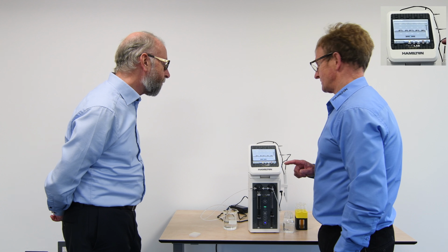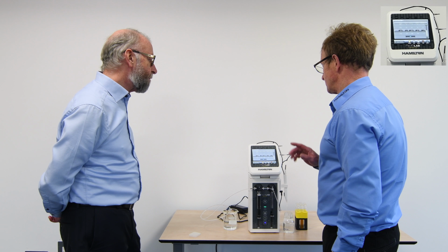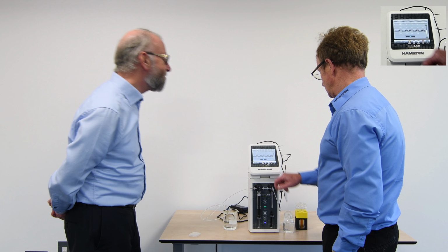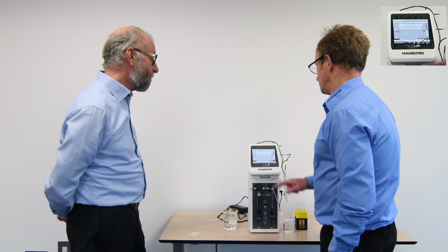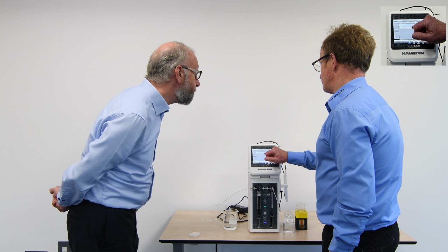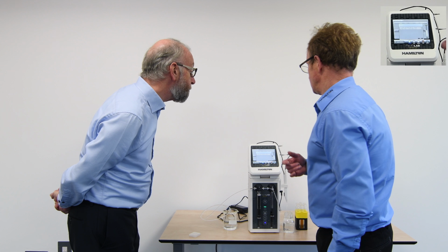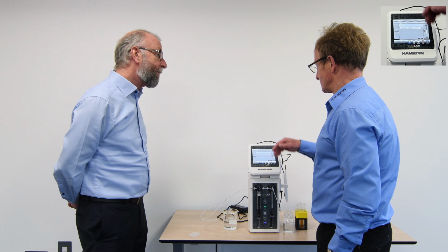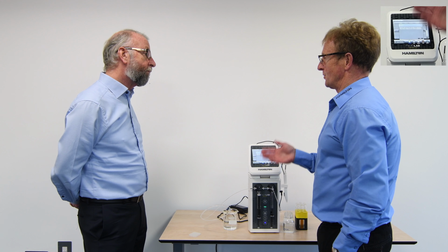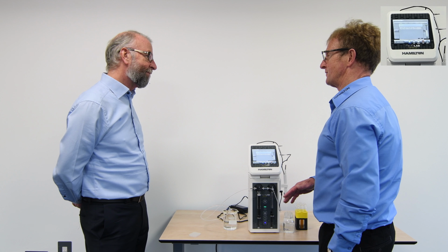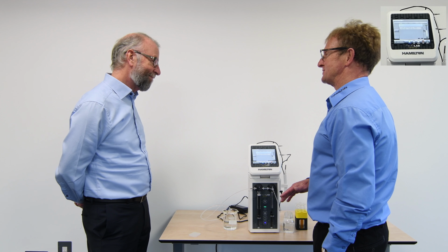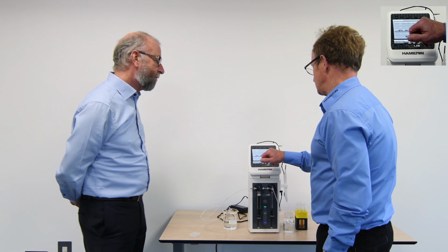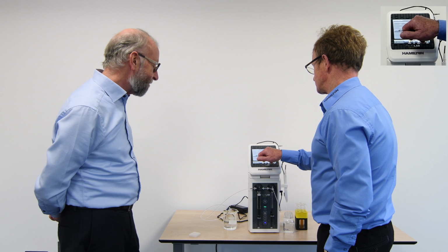Now, if I'd forgotten to actually change the other details, the good step in this is you'll notice this little icon here, it says validate. If I actually press validate here, you'll see this says the method will cause an overaspiration or dispense. So there is initially an error because we've asked it to aspirate more than we're dispensing, and therefore there's an imbalance. It's our spreadsheet of information there. So there's an error and it's told us where it is, which actually here is the fact that I wasn't dispensing the correct amount.